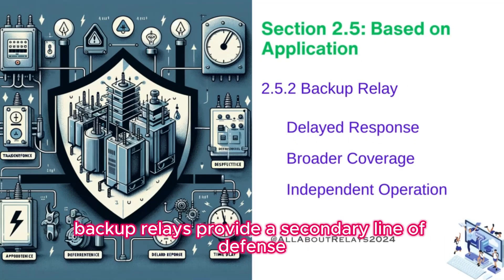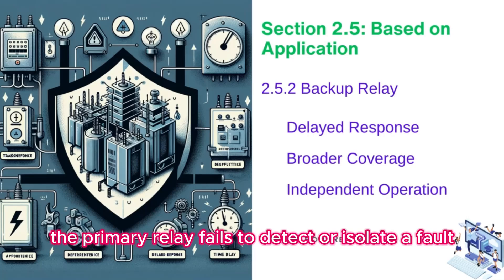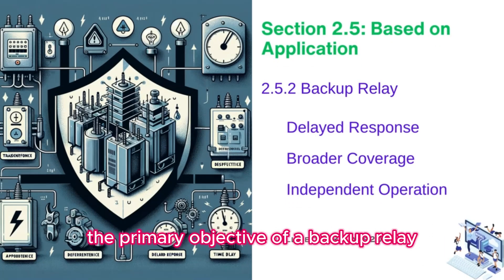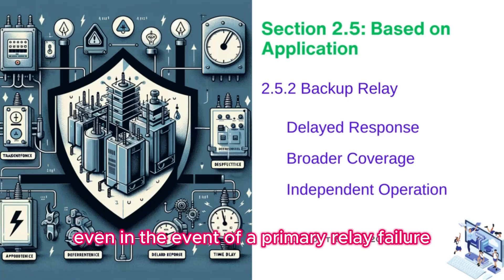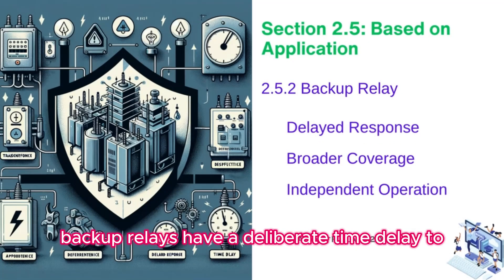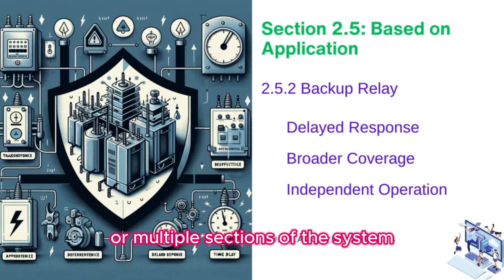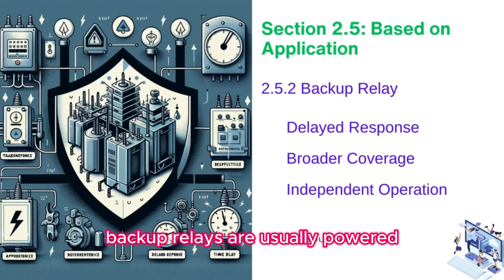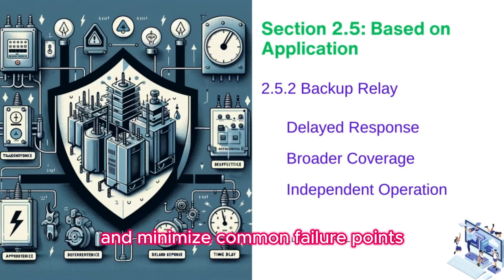Backup relays provide a secondary line of defense. They are designed to operate in case the primary relay fails to detect or isolate a fault. The primary objective of a backup relay is to ensure system protection is maintained even in the event of a primary relay failure. Unlike primary relays, backup relays have a deliberate time delay to allow the primary relay to operate first. They often cover a larger area or multiple sections of the system to provide overlapping protection, and are usually powered and controlled independently from the primary relay to minimize common failure points.